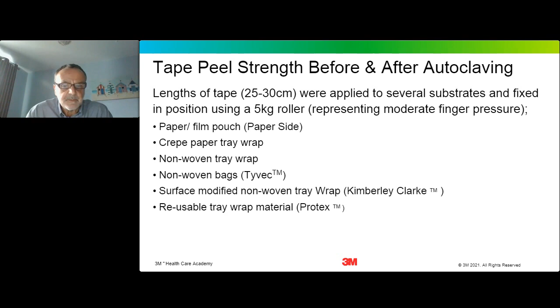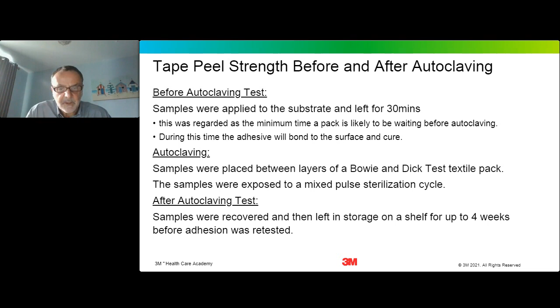So after application, the samples were left to cure for 30 minutes. This was judged as the minimum time between the application of a tape and when the autoclave process would be carried out. And of course, during this time, the adhesive would bond to the surface and begin to cure. Samples were then placed between layers of textile material to represent real-time use, and then exposed to a steam sterilisation processing cycle. Samples were then stored for up to 4 weeks before retesting in a post-autoclaving adhesion test. So the adhesion of the tapes before and after autoclaving were then determined.